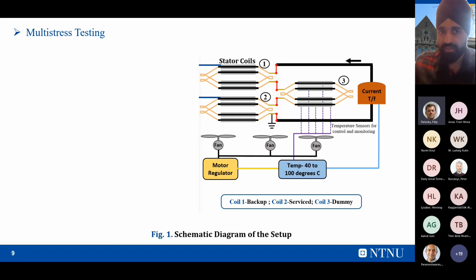Now this one or two have some extra blue lines. Basically these are the connections for the voltage stress. Coils 1 and 2 of the hydrogenerator are stressed by the voltage profile of the rated value. So there is this voltage transformer, and in between, these blue dotted lines are an online partial discharge monitoring. What is partial discharge? I will explain this in the further slides. This is continuous online monitoring: while I conduct the entire test, I keep measuring the partial discharges inside these windings. So now winding 1 and winding 2 are stressed by the voltage and also the thermal effect. Basically this is called multi-stress testing.